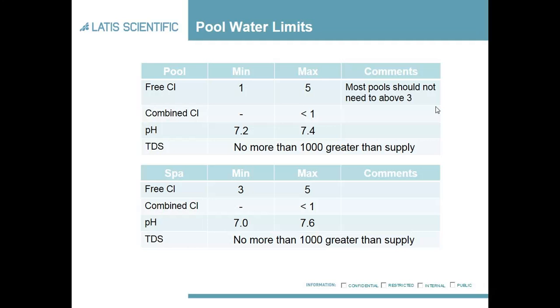For spas, the free chlorine, because of the increased risk, the minimum is three and the maximum is still five. The combined chlorine is still the same levels, which is less than one. The pH is a slightly wider but starting lower range of seven to 7.6, and that's because of the increased risk in spa pools. The TDS is exactly the same as the pools — no more than a thousand greater than the incoming supply.